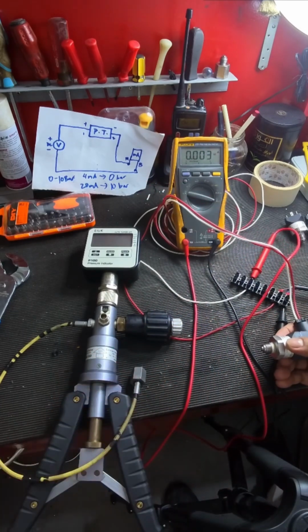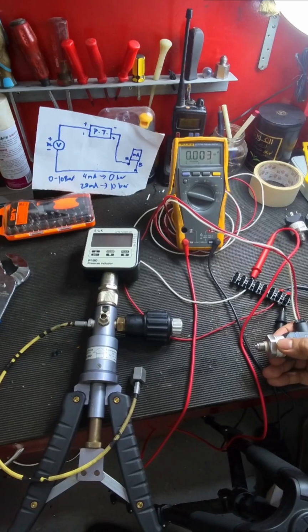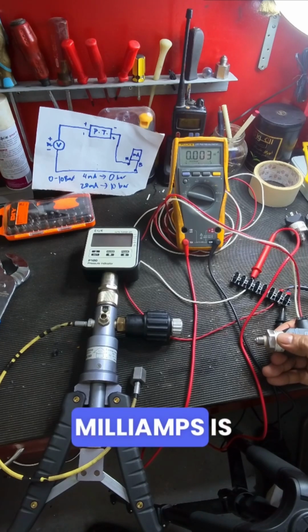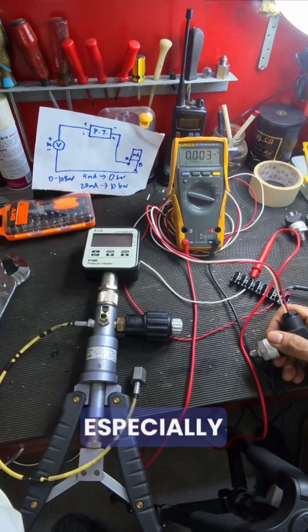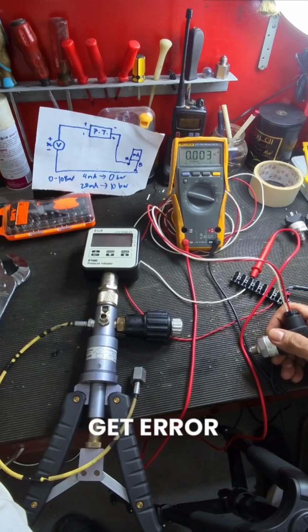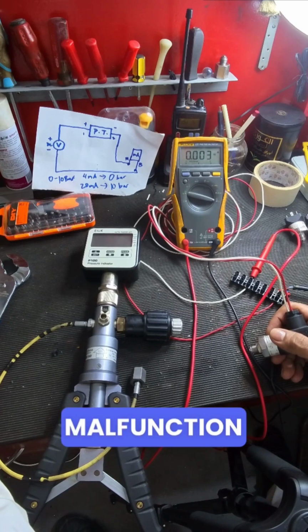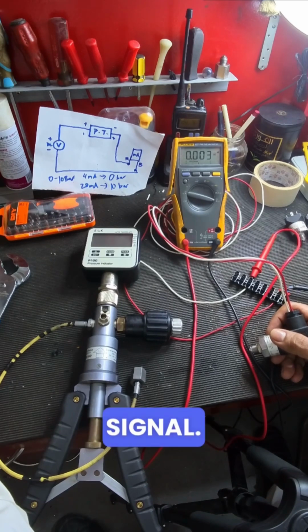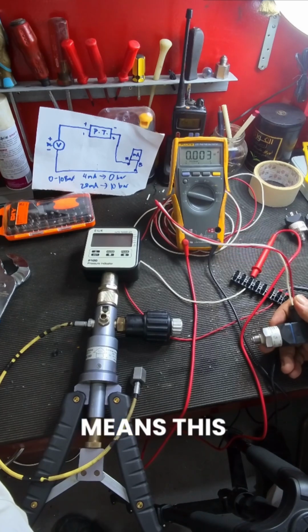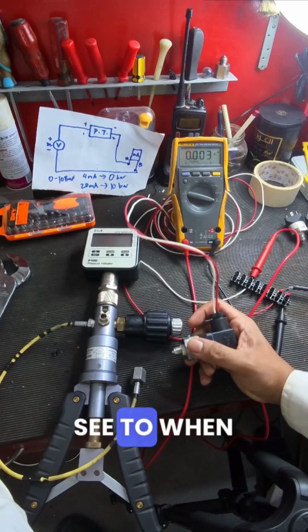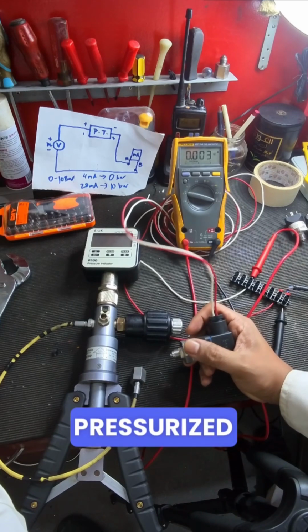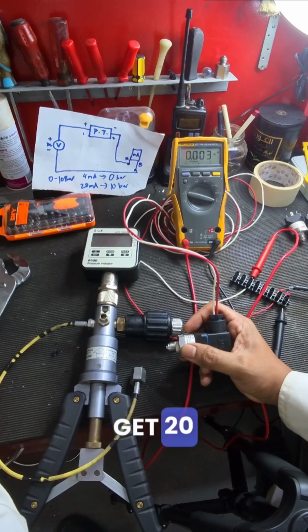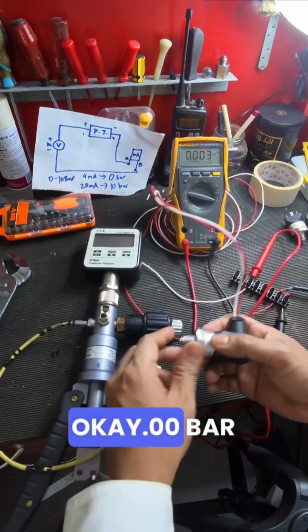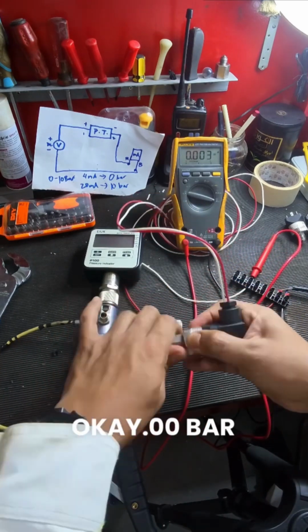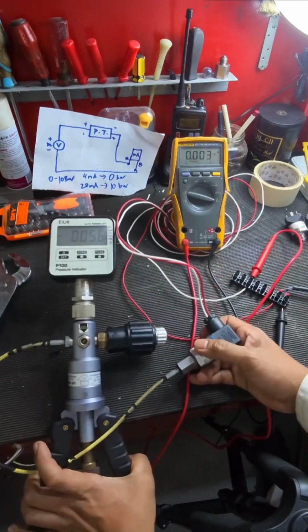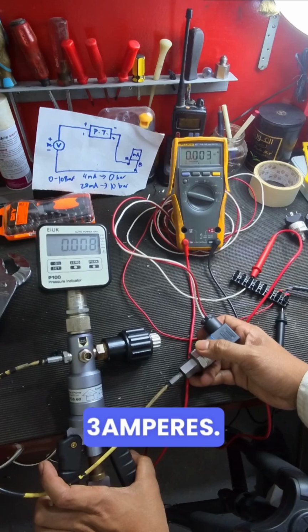This needs adjustment, because 3 milliamps is not acceptable, especially to the PLCs. The PLC will get an error or malfunction, because it cannot accept this output signal of 3 milliamps. So this sensor already has some problem, but we will see when we pressurize the system. When the sensor becomes pressurized, it should get 20 milliamps at maximum pressure. Okay, 0 bars, 3 milliamps reading.